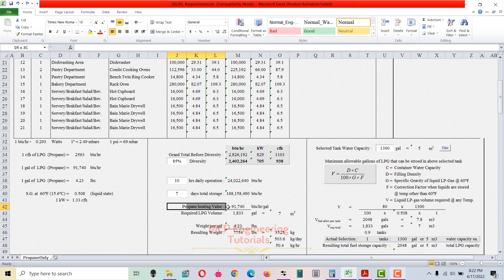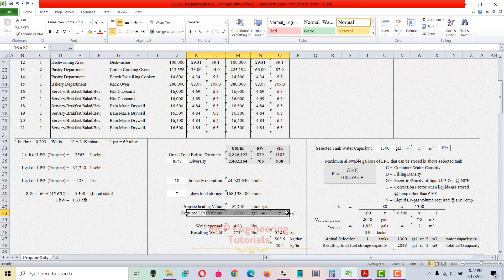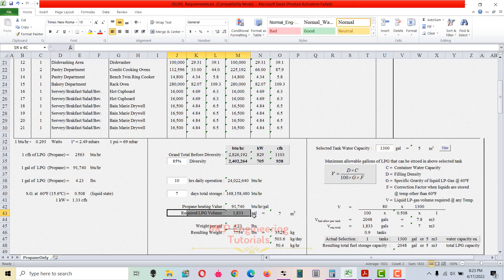The propane heating value is 91,740 BTUs per hour. To calculate the required LPG volume, divide the total storage for 7 days at 10 hours operation by this heating value — divide by 91,740. The required volume is 1,833 gallons, which is approximately 7 cubic meters.